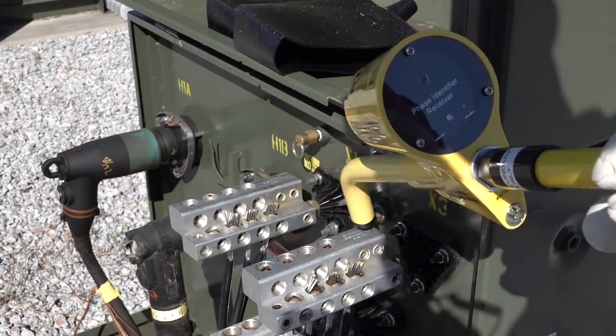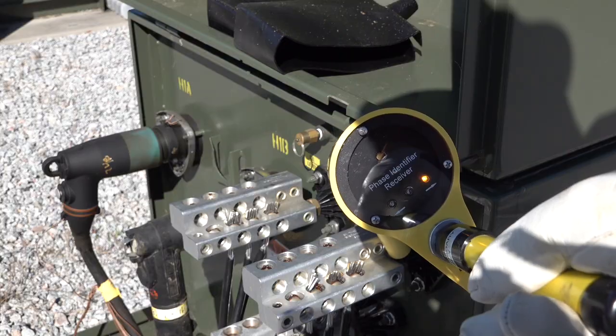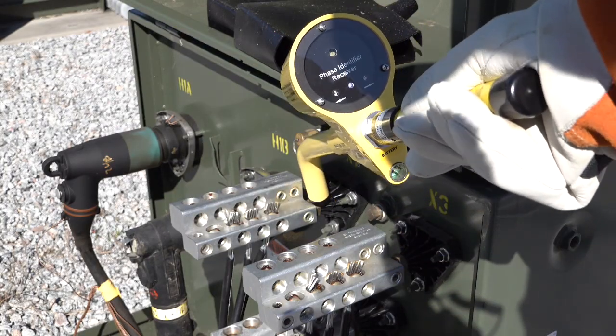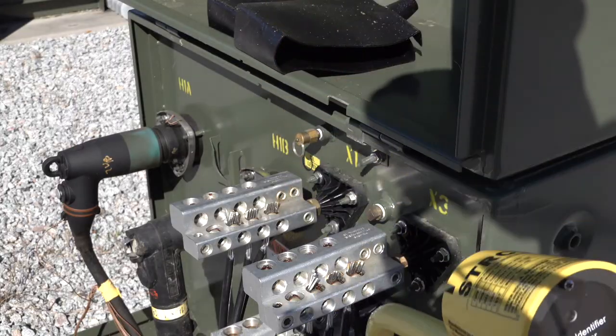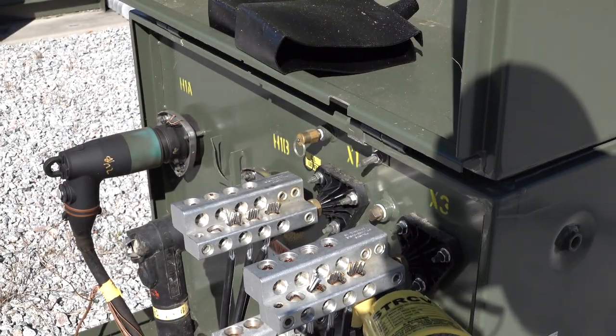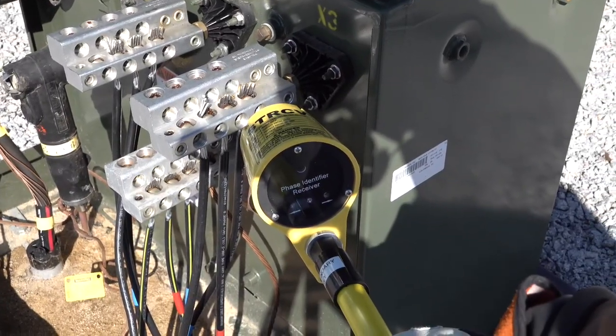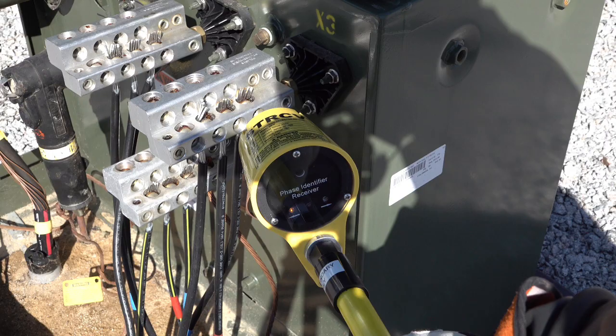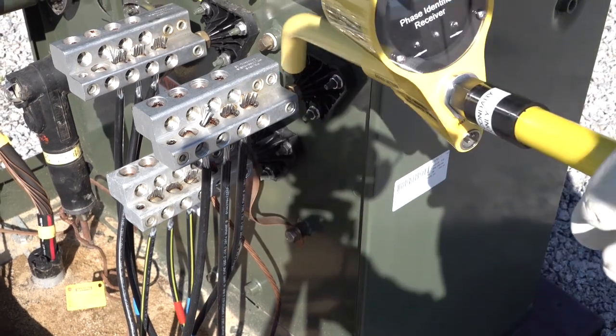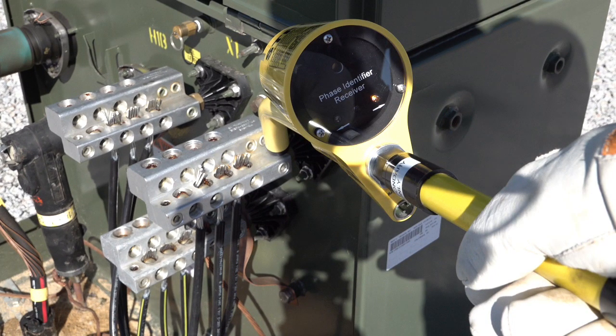If the situation ever occurred where you're unsure where the service is fed from, a preliminary check at the bushings can be made to verify the source of power for the service. Again, notice the direction of the arrow and the indicating LED. With the arrow pointing to the left, this indicates that the neutral is still connected to the black lead of the ST800, since the pulse is going back to the ST800. With the arrow pointing to the right or into the transformer, this indicates that it's still connected to the red lead of the ST800 since the pulse is going away from the ST800.